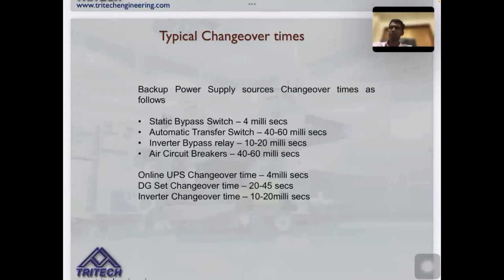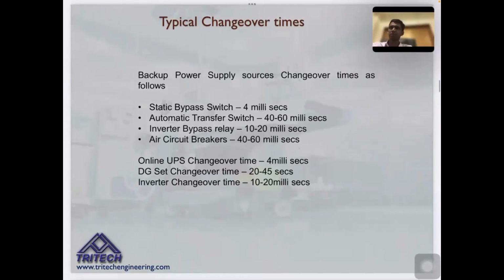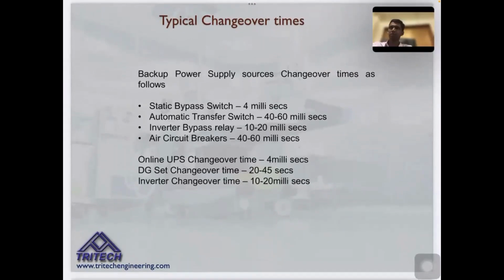If you look at all these devices, the typical online UPS changeover time will be around 4 to maybe 6 milliseconds, which will not affect any of your digital equipment. Then we have the DG set changeover, which is the start, stop, synchronization and closing time, which may be somewhere around 20 to 45 seconds. The inverter changeover time is also mentioned here.